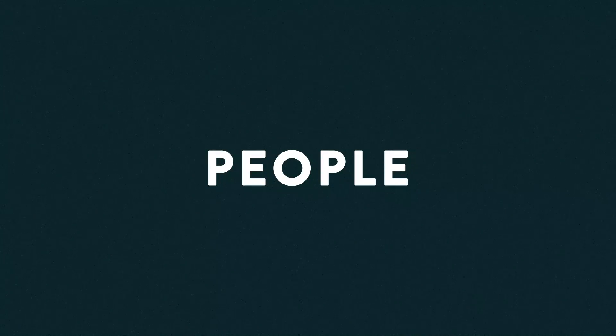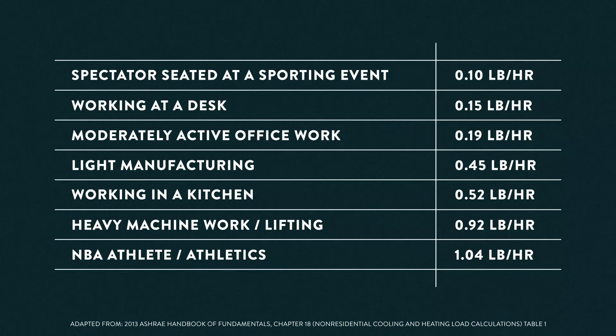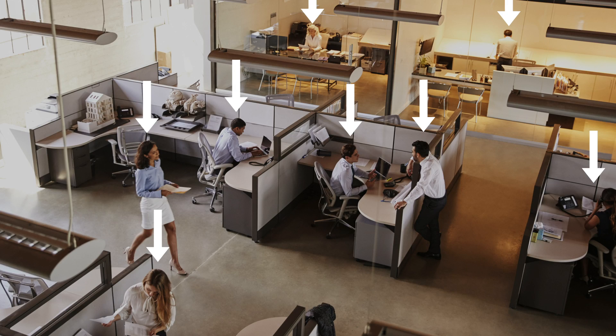Let's look at the first one: people. When we start looking at our loads, we need to look at what are the people doing and how much humidity do they add to the building. Let's go to a table such as this. On this table, we can see various activities and the amount of moisture load associated with it — everything from a spectator seated at a hockey game or a basketball game putting off a tenth of a pound of water per hour, to somebody working at a desk, light activity, light manufacturing, or working in a kitchen, ranging from a quarter up to a half a pound per hour. As people get more active, they put off more sweat, and that translates into more moisture, all the way up to an NBA athlete putting a pound per hour or more into that space. We need to know what they're doing and when they're doing it, and if that is at the peak time that we're trying to take the moisture out of the building. So what you need to do for the people load is take a head count: how many people are in that space and what are they doing? What's their activity level? So we can determine how much water they're putting into the air. Based on that, we've now got our people moisture load.